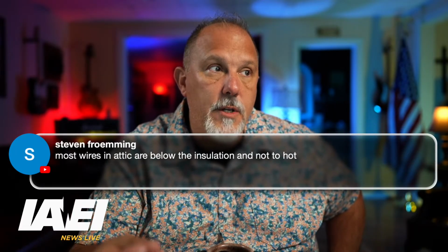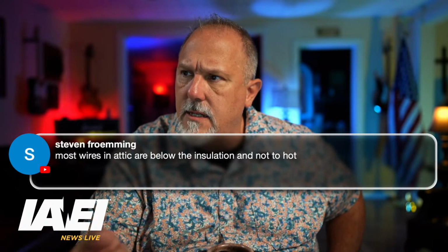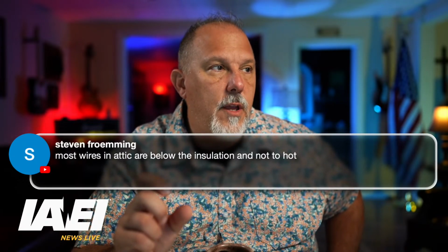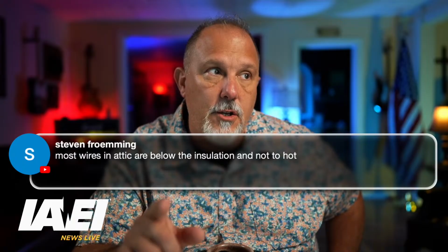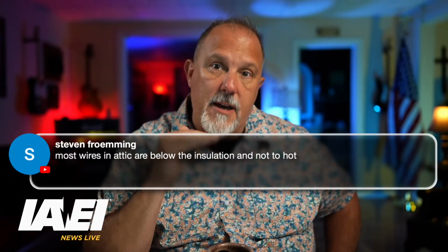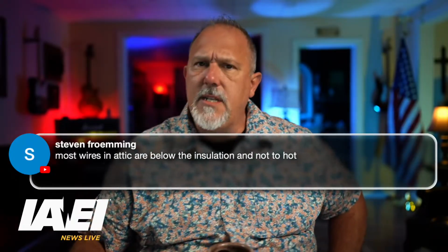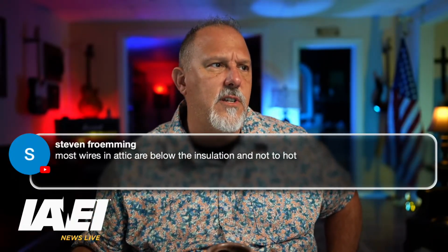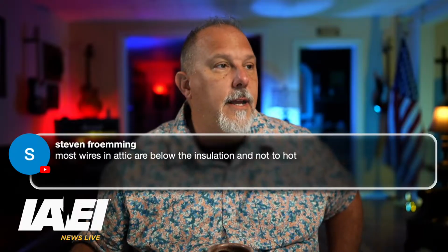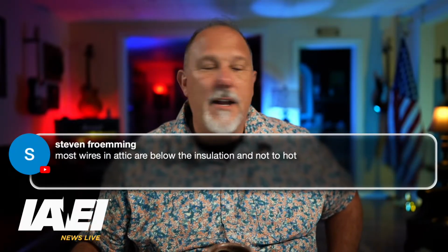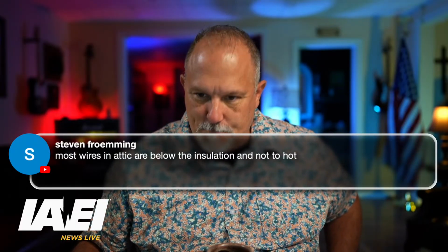So if it gets hotter than 86, you're going to need to reduce the amount of current passing through that. But I probably tend to agree with you that you're not going to exceed 194 in an attic. If you've got more than 194, then you've got other problems, right? I would agree with you there.